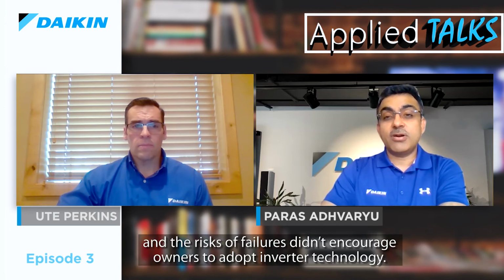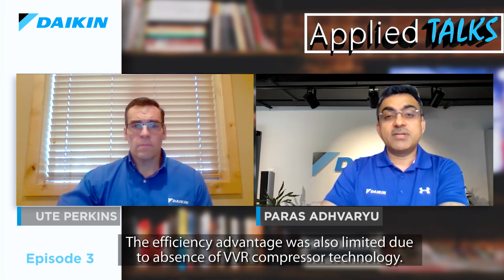Definitely. In the past, due to unavailability of refrigerant-cooled inverter, air-cooled inverter or glycol-cooled inverter reduced the reliability of this technology and chiller as a whole, and the risks of failures did not encourage owners to adopt inverter technology. The efficiency advantage was also limited due to absence of VVR compressor technology.